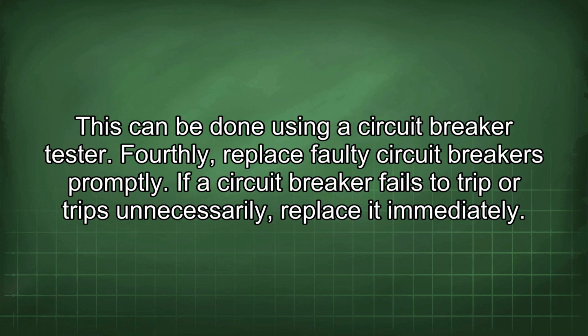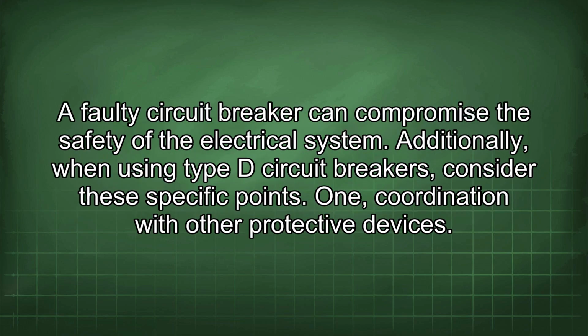Fourthly, replace faulty circuit breakers promptly. If a circuit breaker fails to trip or trips unnecessarily, replace it immediately. A faulty circuit breaker can compromise the safety of the electrical system. Additionally, when using Type D circuit breakers, consider these specific points.